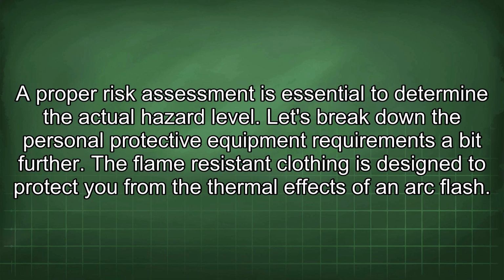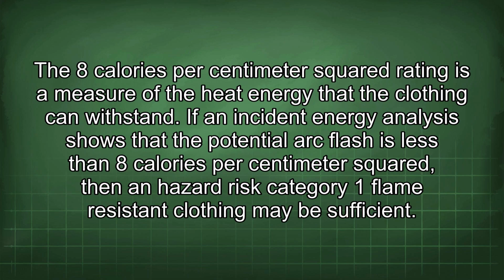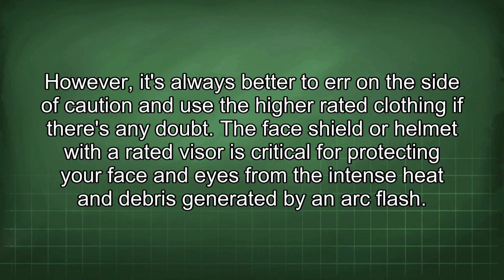Let's break down the personal protective equipment requirements a bit further. The flame-resistant clothing is designed to protect you from the thermal effects of an arc flash. The 8 calories per centimeter squared rating is a measure of the heat energy that the clothing can withstand. If an incident energy analysis shows that the potential arc flash is less than 8 calories per centimeter squared, then hazard risk category 1 flame-resistant clothing may be sufficient. However, it's always better to err on the side of caution and use the higher rated clothing if there's any doubt. The face shield or helmet with a rated visor is critical for protecting your face and eyes from the intense heat and debris generated by an arc flash.